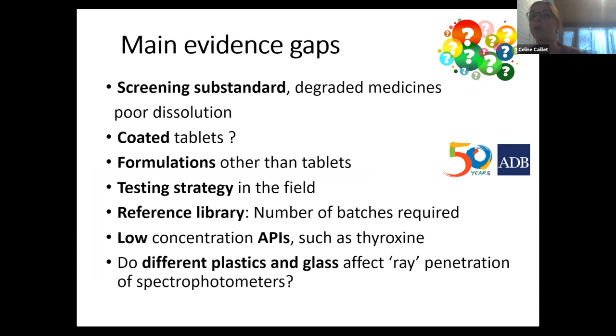There is also not much evidence on how coating of tablets will interfere with screening device signals, especially spectrophotometers. There is a lot of information on tablets, but not on other formulations like capsules, vaccines, or injectables. Testing strategy in the field — how many times do you test the same sample — is another gap, as is the reference library, specifically the number of batches required to account for inter-batch variability. Some medicines contain very low concentrations of active pharmaceutical ingredients, such as thyroxine, and some devices cannot detect those. And for devices that can screen through packaging, how different plastics and glasses affect ray penetration is also not well understood.